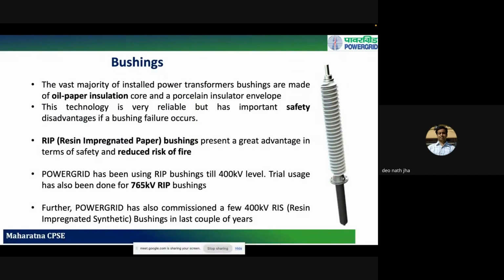In terms of bushings, the vast majority of installed power transformers are made with oil paper insulation. So inside a bushing, there will be a paper insulation, and the bushing will also be filled with oil as an insulating medium. This is very reliable technology, but has important safety disadvantages, such as if the bushing fails, then the oil will spread across the transformer and it can lead to fire. So nowadays, resin impregnated bushings have been introduced, where instead of oil, the bushings are filled with epoxy resins to avoid fire in the bushings or the transformer in case of any failure.